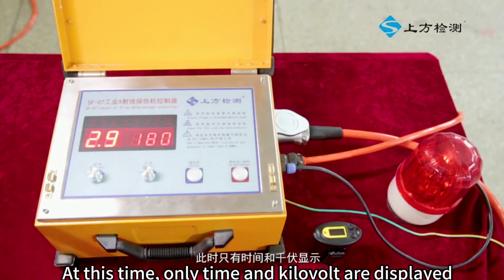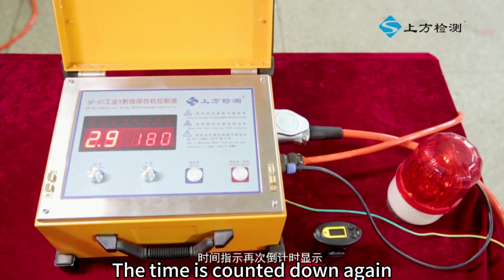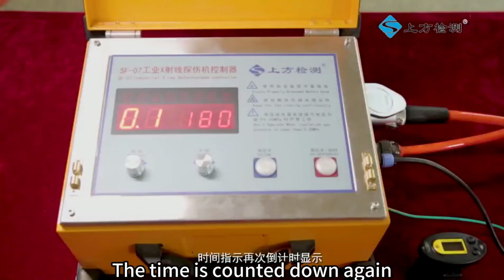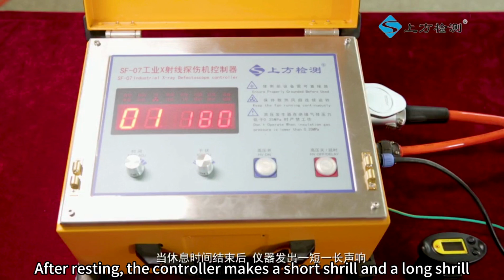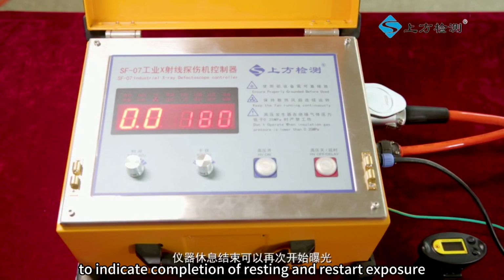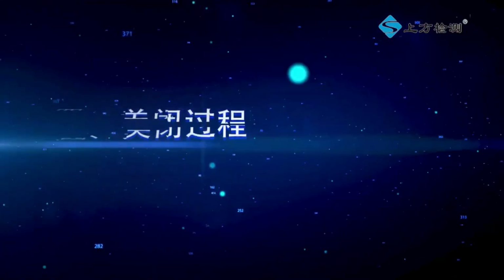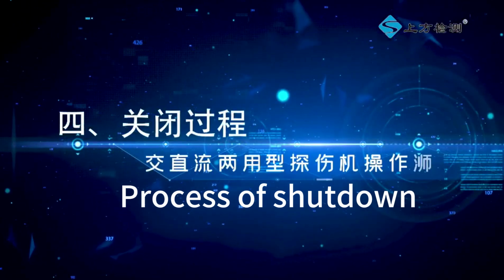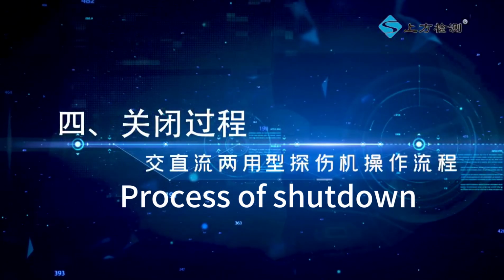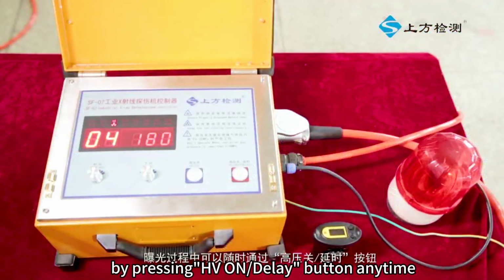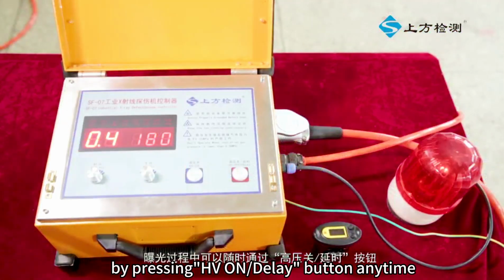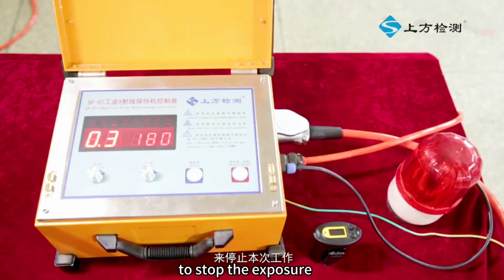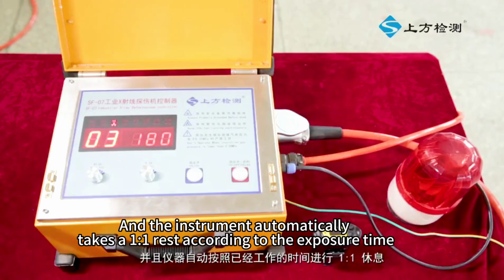At this time, only time and kilovolt are displayed. The time is counted down again. After resting, the controller makes a short shrill and a long shrill to indicate completion of resting and restart of exposure. 4. Process of shutdown. Press the HV on/delay button anytime to stop the exposure, and the instrument automatically takes a 1:1 rest according to the exposure time.